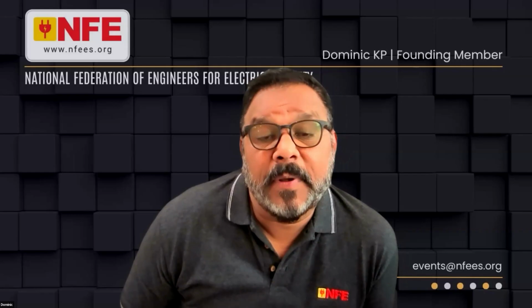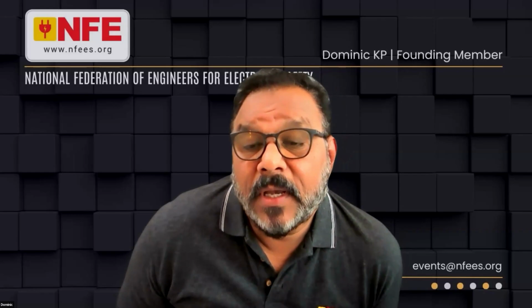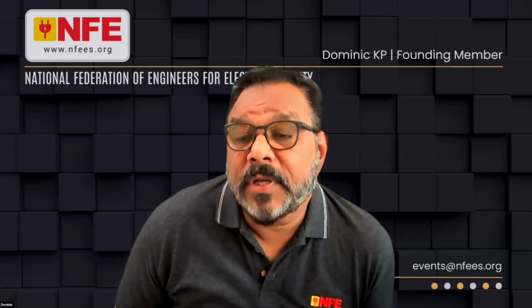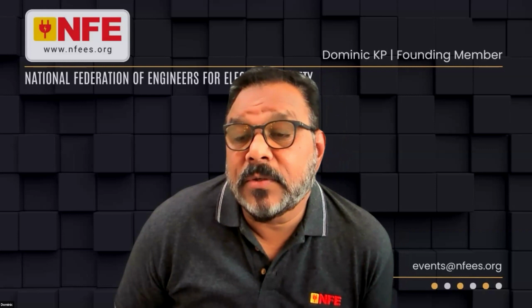Bharat Yadav is asking, different cable manufacturers and cable sizes have different diameters and conductor compaction. How do we ensure that the kit is truly the best selection for each layer? Generally this depends on the compactness. Some companies have greater compactness, some don't. It is taken care of by the ferrules, because there is a crimping ferrule and we do the crimping activity, so it crimps properly. If it is a joint, and both cables are the same make, that will not be an issue. If it is a mechanical ferrule, it has the property to take care of slight variation in conductor sizes. The rest, the XLPE insulation and semiconducting layer, is the same. So cable accessory manufacturers take care of all these things.